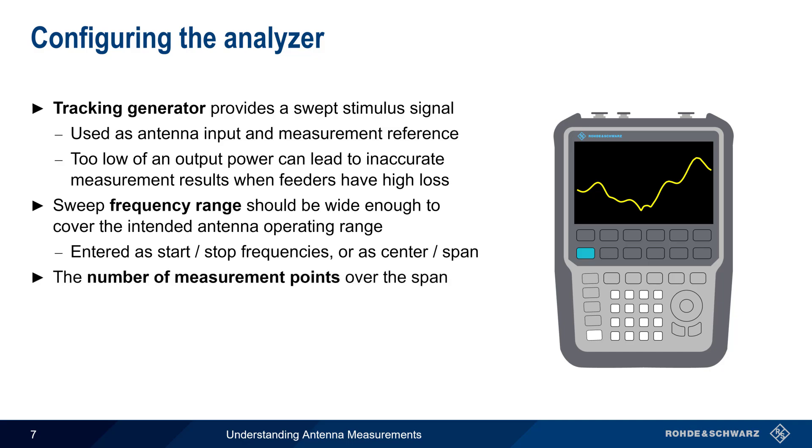The third important parameter is the number of measurement points over this span. Increasing this number beyond the analyzer's default settings will provide greater detail, but more frequency points will also increase the amount of time needed to make a single sweep.